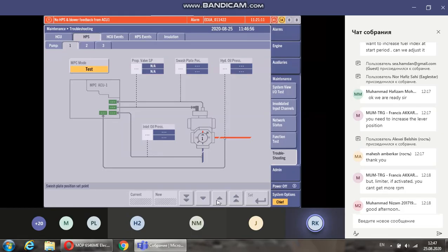after some time, pressing the arrow keys at the bottom. If we have plus 100, that is going to equate to 100% ahead, i.e. 15 degrees position of our swash plate. If I set it to minus 100, then I am setting it to astern position on the swash plate, i.e. 15 degrees astern. And at 0, the swash plate is in the center point. I can also check down on the position of the pump. There is an indication of where the pump swash plate is.